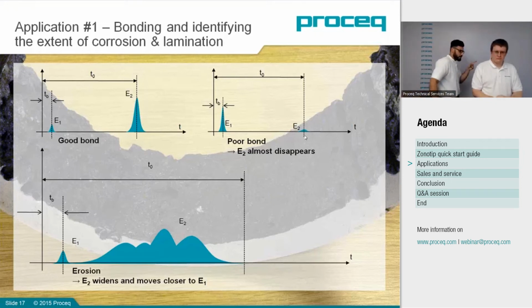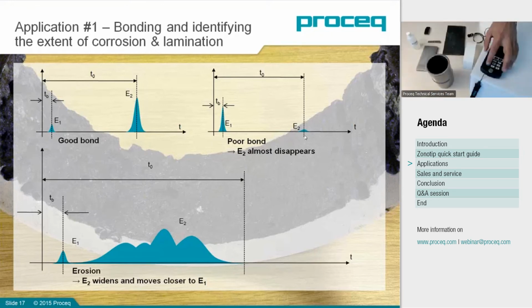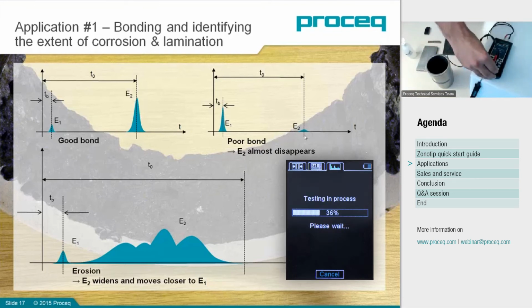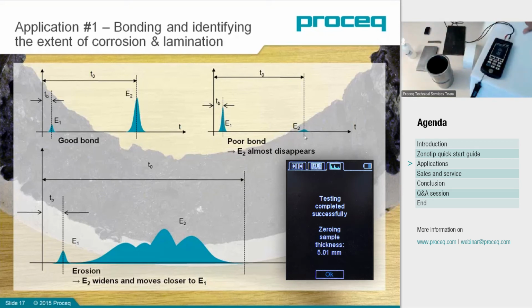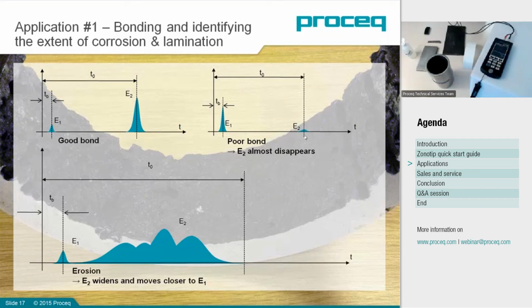On that note, I'm going to go to the demo table that we've got for you here. The first thing I would like to do is switch on my device and start the demo. First, I need to tell the device what probe I've connected to it. As you can see, I'm going to choose the 4 megahertz transducer. It's going to tell me to make sure there's no coupling on it, and enter. Next step, it will ask me to apply some coupling paste, as you can see over here, and place it on the test plate on the front and then enter. This is pretty much the zeroing process. Then I press OK, and I'm good. Coming back out of the device, it takes me straight to the main menu.